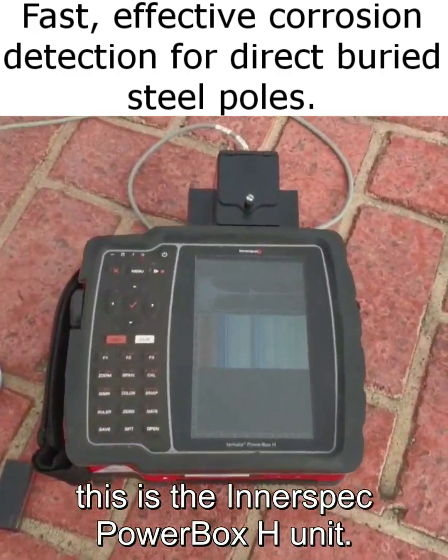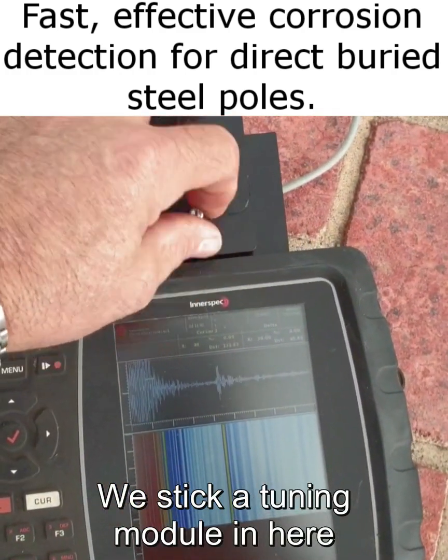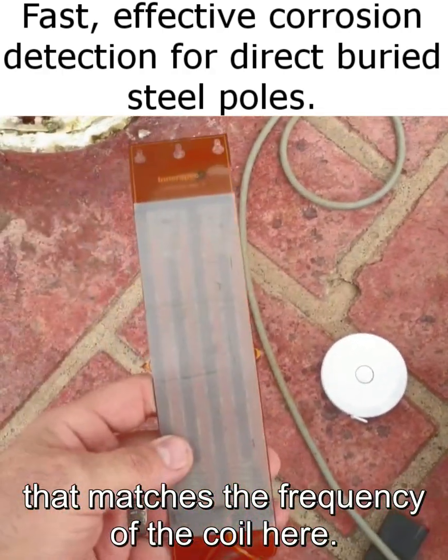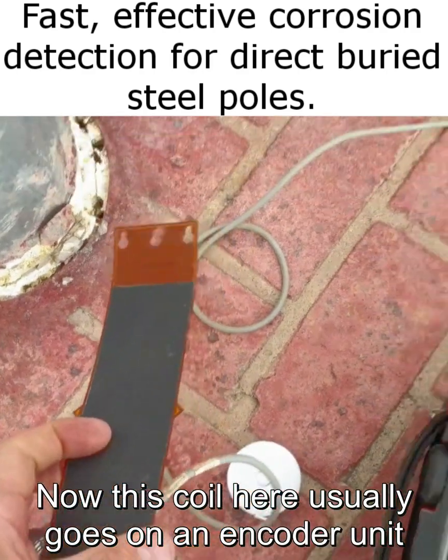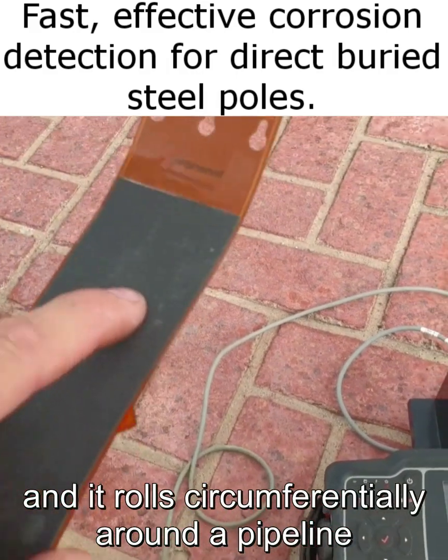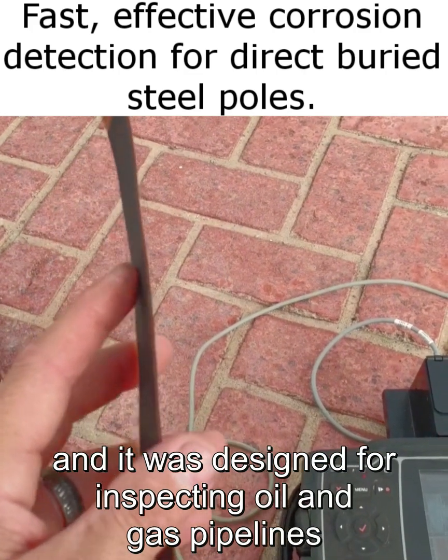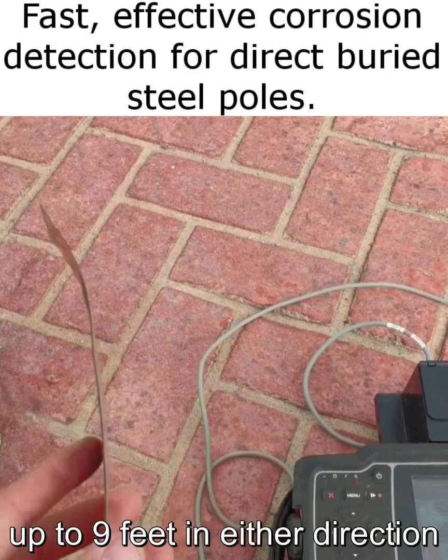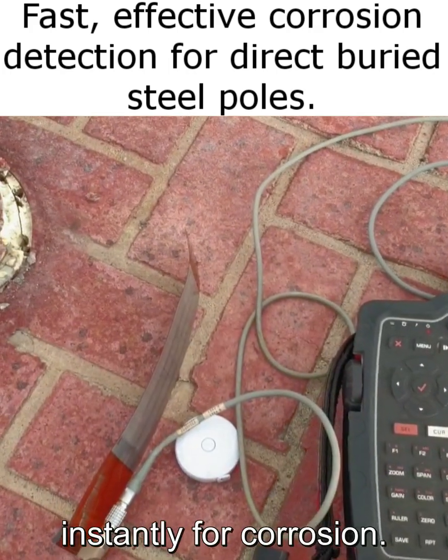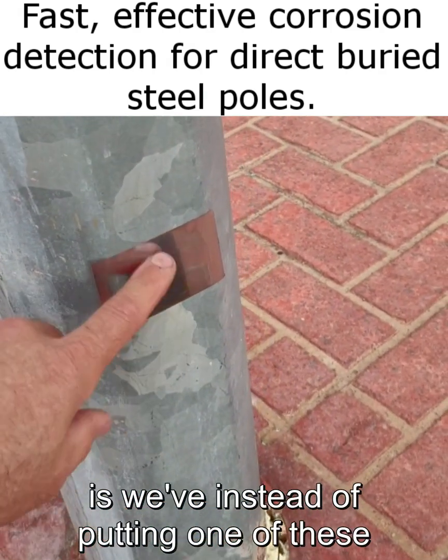This is the Innerspec PowerBox H unit. We stick a tuning module in here that matches the frequency of the coil. This coil usually goes on a fancy little encoder unit with wheels that rolls circumferentially around a pipeline. It was designed for inspecting oil and gas pipelines out in the field quickly and easily, up to nine feet in either direction, for corrosion.